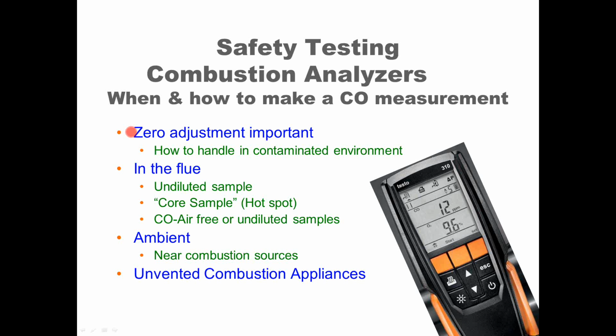If you do have it in a contaminated environment, it'd be great if you had a personal CO monitor and you could understand how much is present when you're starting up and zeroing it, and you could subtract that from the reading to see what the total concentration was. Or being able to actually move outdoors and start up the analyzer when you are outdoors.